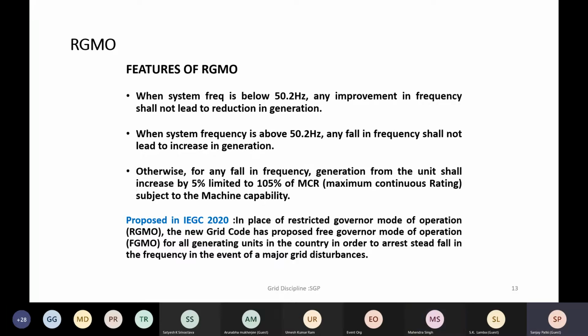But this also will be helpful for thermal power stations which have online reserve capacity. If, as per the merit order, they are operating on part load, they will be the ones which will basically play a role. And the rate at which a thermal power station can vary its generation, increase or decrease, again depends on the master fuel control on the boiler side. So each generating station, whether thermal or hydro, will have to respond at a rate according to the recommendations of the respective manufacturers and the type of plant, so that pressure variations or spillage, etc., do not occur. That is one of the things.